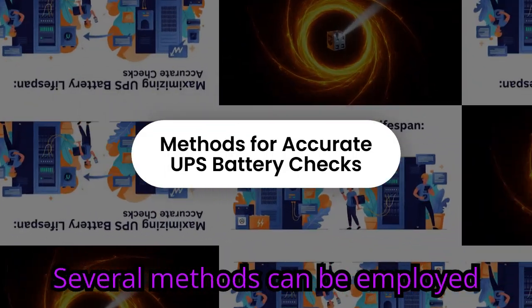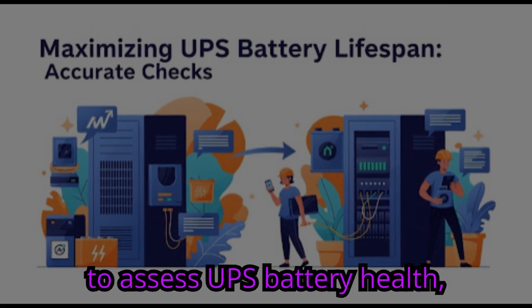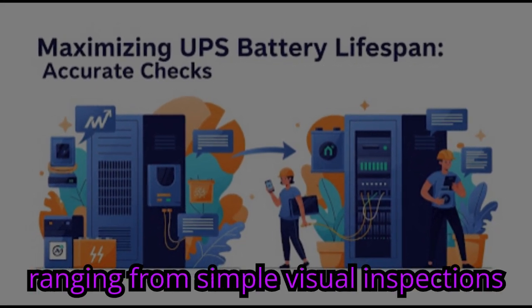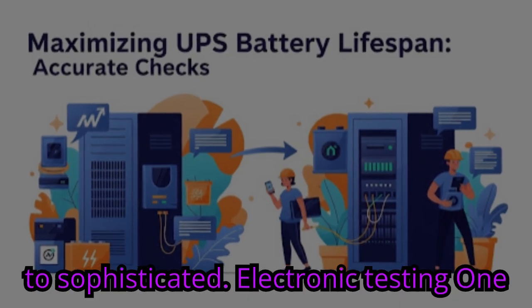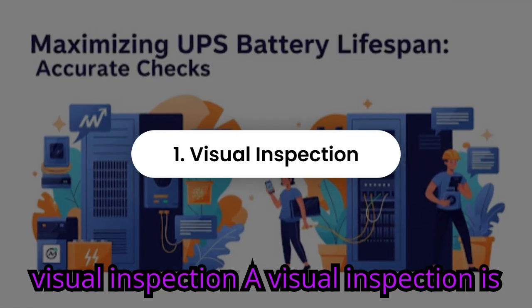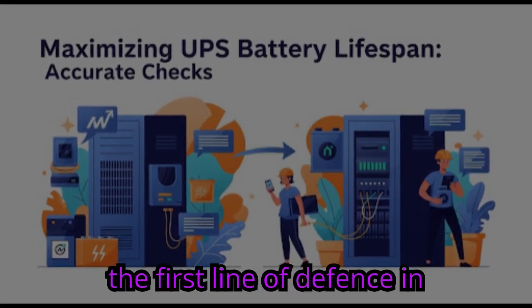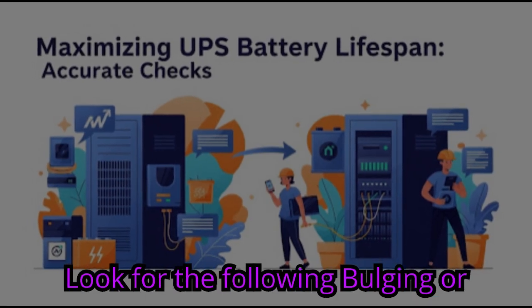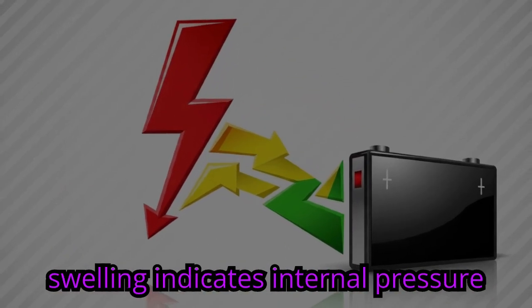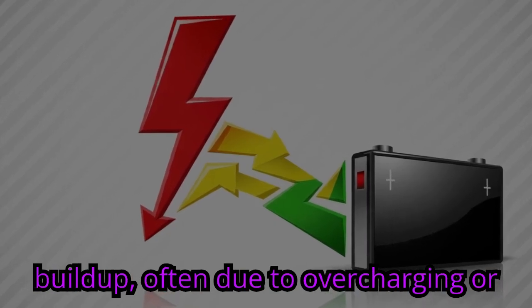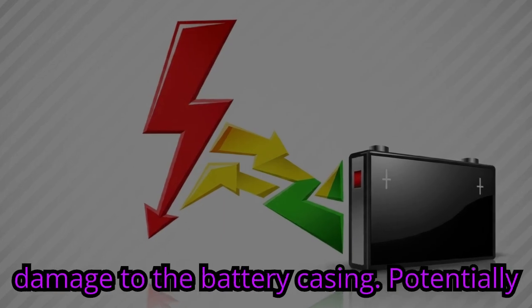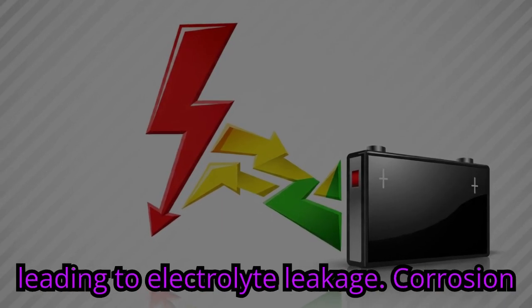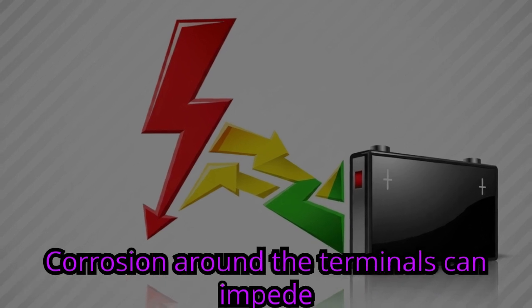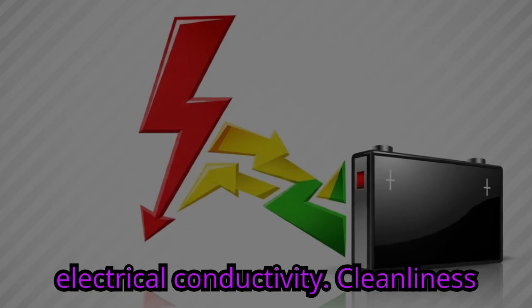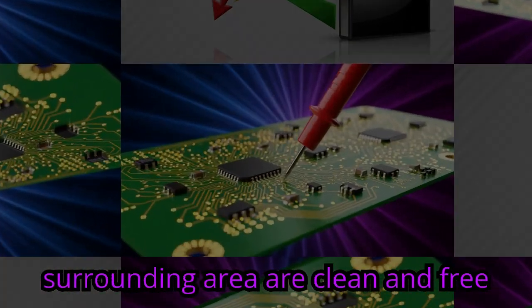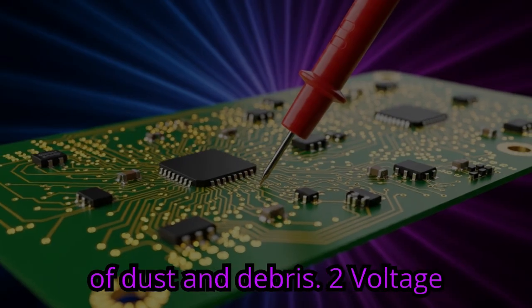Methods for accurate UPS battery checks. Several methods can be employed to assess UPS battery health, ranging from simple visual inspections to sophisticated electronic testing. 1. Visual inspection. A visual inspection is the first line of defense in identifying potential battery problems. Look for the following. Bulging or swelling indicates internal pressure buildup, often due to overcharging or overheating. Cracks or leaks signifies damage to the battery casing, potentially leading to electrolyte leakage. Corrosion. Corrosion around the terminals can impede electrical conductivity. Cleanliness. Ensure the battery terminals and surrounding area are clean and free of dust and debris.